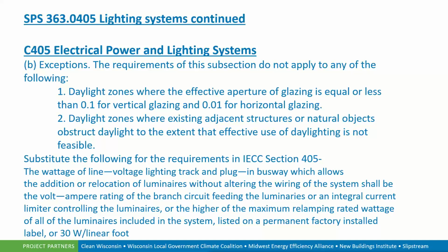There are some exceptions, as with everything within the code, and they don't apply to certain areas. As you can see with the daylight zones where the effective aperture of the glazing is less than 0.1 for vertical or 0.01 for horizontal, and where adjacent structures or natural objects obstruct daylight zones. So if we have buildings closer together, where one building shields certain areas from sunlight so that we're not affecting the daylight area or daylight zoning, then there are some requirements that we can follow. As you can see, there is a substitution for the line voltage track plugs within this section, and this is on permanently installed factory equipment. So again, make sure we follow that substitution of the code in section 405 for line voltage lighting track lighting.